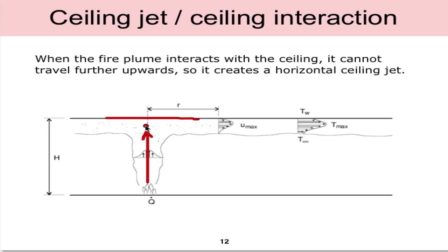What happens if we introduce a ceiling as in an enclosure? The hot gas is traveling upward due to buoyancy, can no longer travel upwards, so it creates this horizontal ceiling jet that travels in all directions. We have a velocity profile, a temperature profile, all in the ceiling jet and outside of this area is assumed to be ambient conditions.